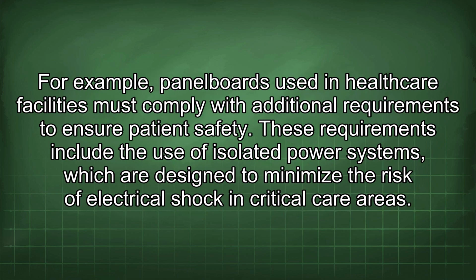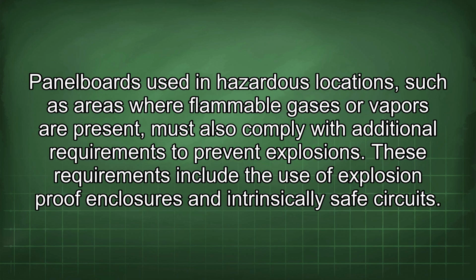For example, panel boards used in healthcare facilities must comply with additional requirements to ensure patient safety. These requirements include the use of isolated power systems, which are designed to minimize the risk of electrical shock in critical care areas. Panel boards used in hazardous locations, such as areas where flammable gases or vapors are present, must also comply with additional requirements to prevent explosions. These requirements include the use of explosion-proof enclosures and intrinsically safe circuits.